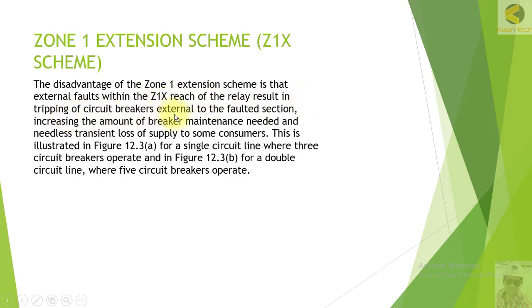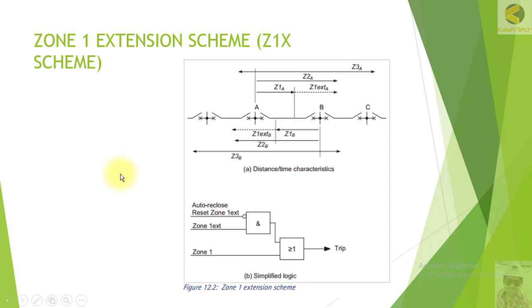The disadvantage of Zone 1 Extension scheme is that external faults within the Z1X reach result in tripping of circuit breakers external to the fault section, increasing the amount of breaker maintenance needed and causing needless transient loss of supply to some consumers. This is illustrated in figure 12.3a for a single circuit where three circuit breakers operate, and in figure 12.3b for a double circuit line where five circuit breakers operate.